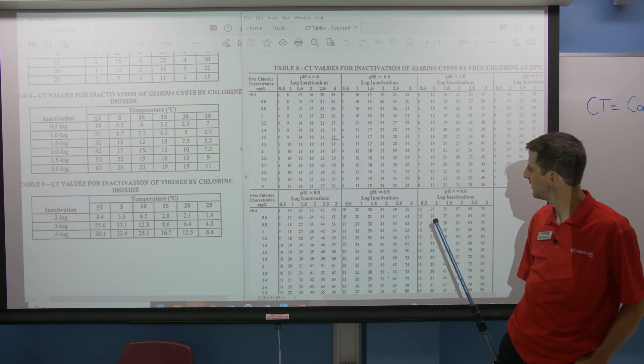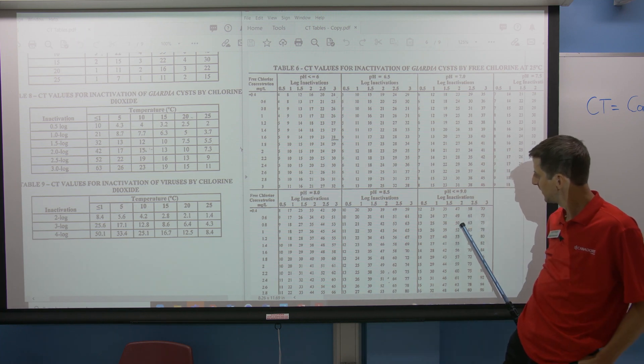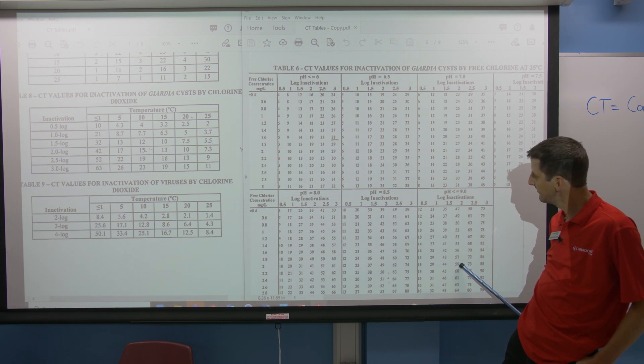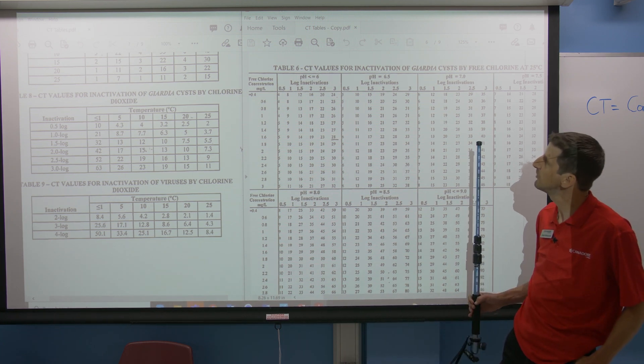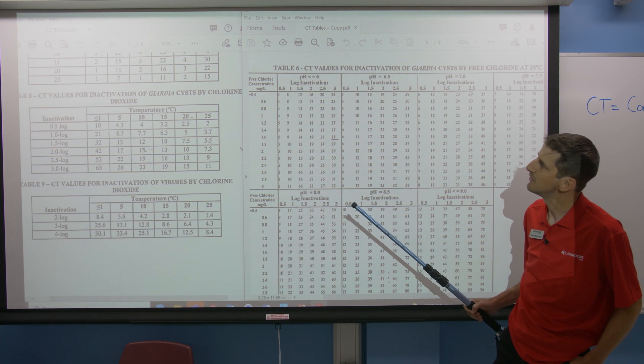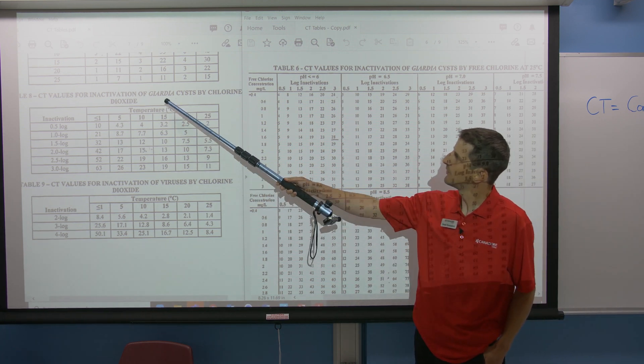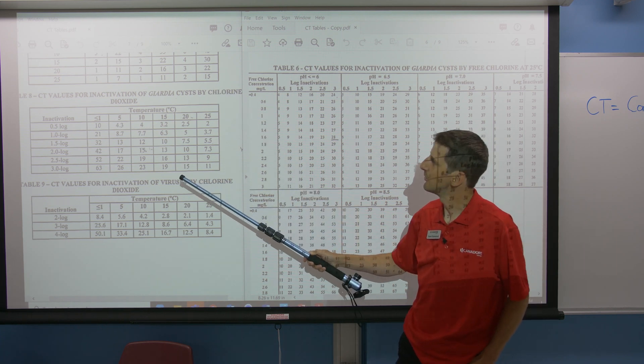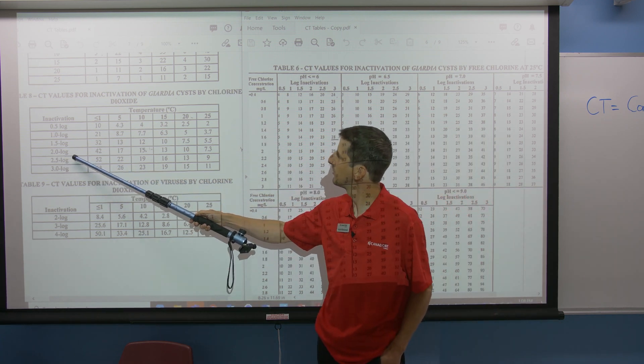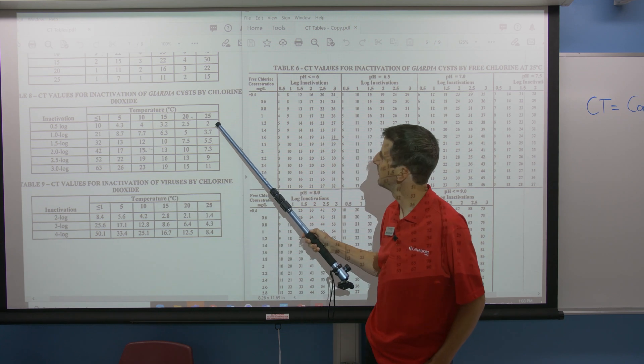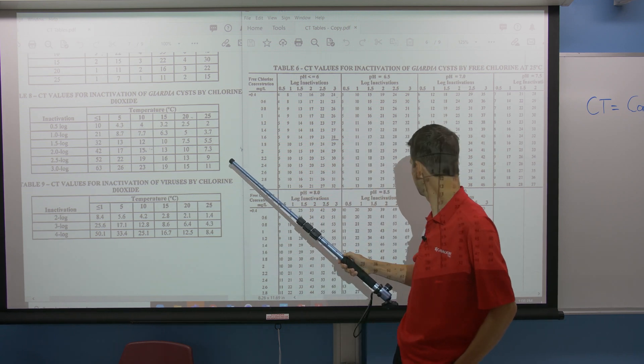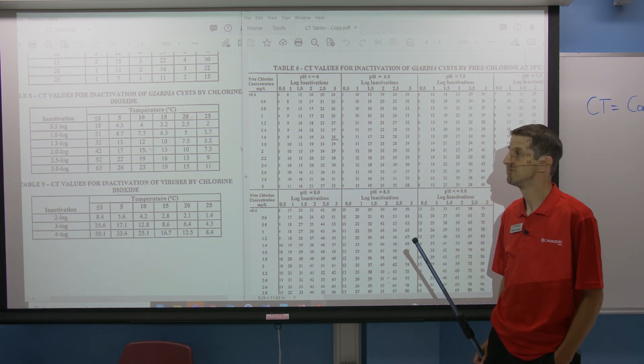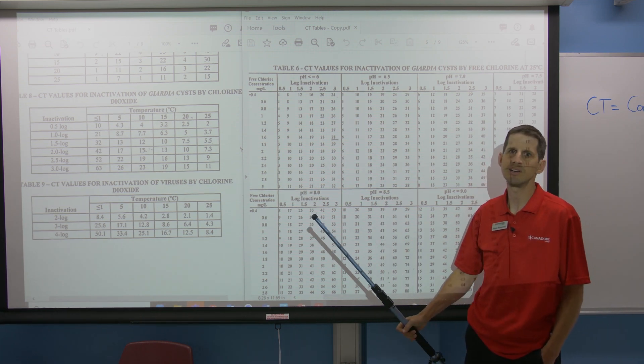Looking at pH 9, 2-log inactivation in Table 6, our CT value was 59. But if you look at Table 8, it's also for inactivation of Giardia, but using chlorine dioxide. At 2-log inactivation and 25 degrees, the CT value is 7.3, compared to 59. So chlorine dioxide is roughly five times more effective for Giardia inactivation.